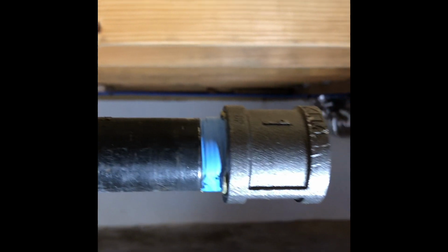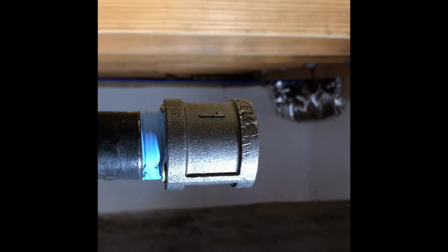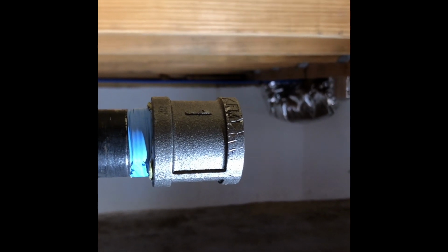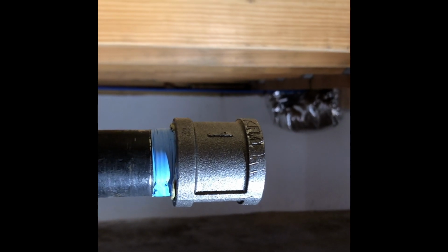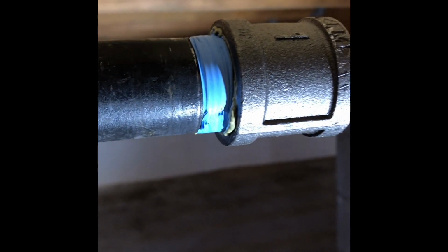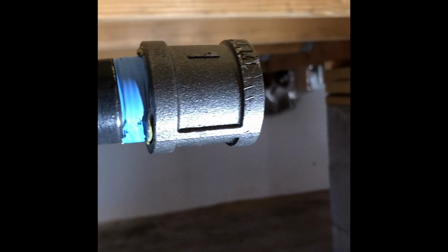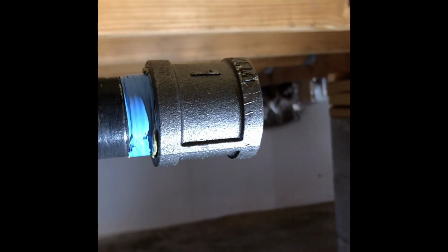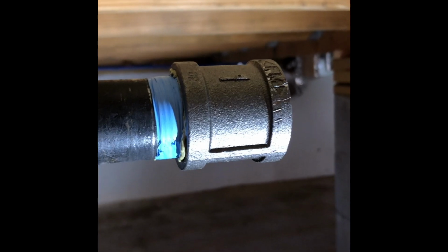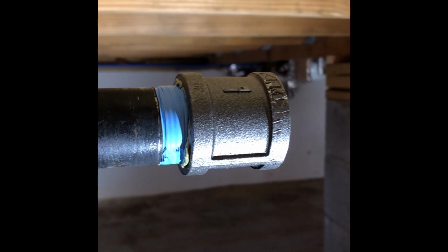All right, I got that fitting on there. I pulled on it pretty hard with a pipe wrench. Some fittings you can manhandle pretty good. That one right there, it'll take a lot. Got a good makeup. You can see the dope pinching and squeezing out from around the tape. The tape stayed nice and snug on the pipe. I can tell you right now, that joint won't leak gas. We can put our test pressure on there, 15 psi, for a 24-hour period. It'll hold it right there.